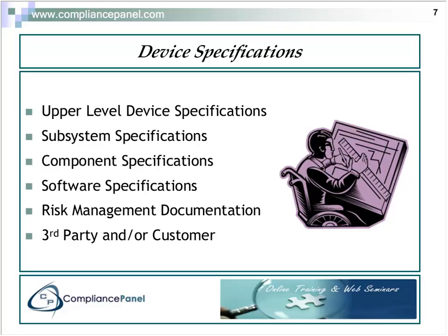And third-party here also, third-party software specifications. There's a lot of devices out there now that include LabVIEW, MathWorks, even Microsoft Office products like Excel may be running as part of a program within your device or during the manufacture of the device, and I'll talk about that a little bit more as well. But third-party software has become a very visible item on the eyes of the FDA, the things that they're looking at, and how you control third-party software, even if it's included in your device.